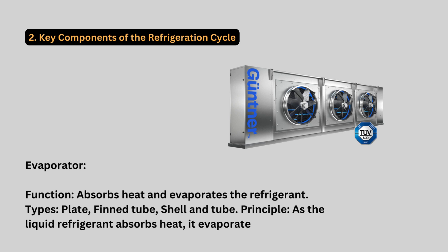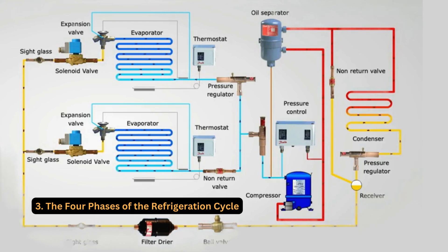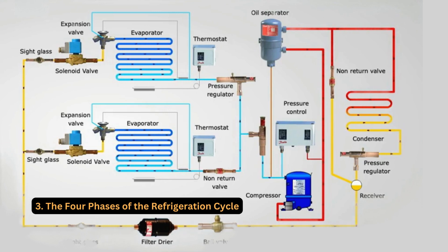Compression: the compressor sucks in low-pressure refrigerant gas, compressing it into a high-pressure, high-temperature gas. This process moves the refrigerant through the system. Condensation: the high-pressure gas travels to the condenser, where heat is removed from the refrigerant, causing it to condense into a high-pressure liquid.